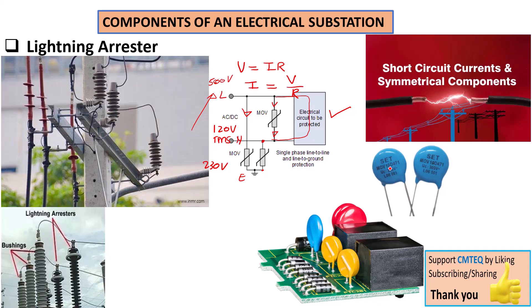This MOV here is marked 10D471. The 10D basically stands for the size — this is a 10mm MOV — and the 471 means the clamping voltage is 471, which basically means 470 volts. As soon as the voltage exceeds 470 volts, this MOV is going to start clamping. You should use it on 300 volts or something less. If you exceed 470 volts, it's going to start clamping and deny current to your equipment, thereby protecting it.